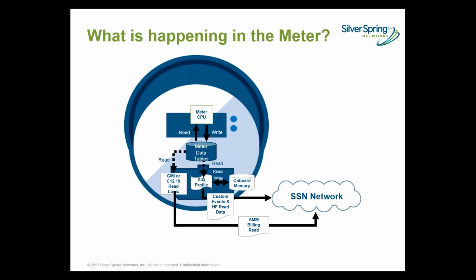At the top of the diagram, you have a meter CPU that's reading various sensors and populating electric data into meter tables based on set intervals. Utilities configure meter programs to read these tables and gather data on a regular basis via their AMI billing read. Normally, after that meter program is set and integrations with downstream systems are in place, you don't want to make constant changes, since billing and outage depend on this information.